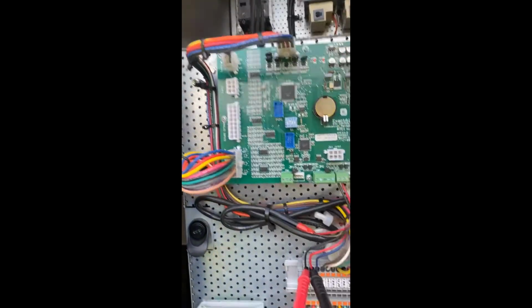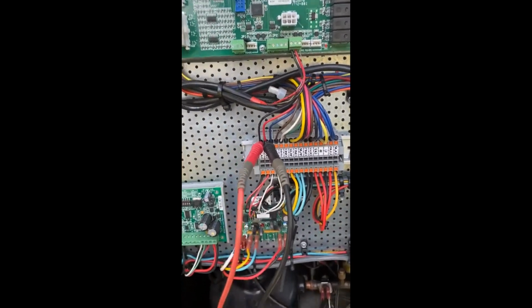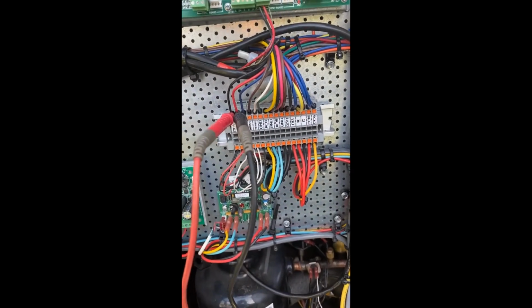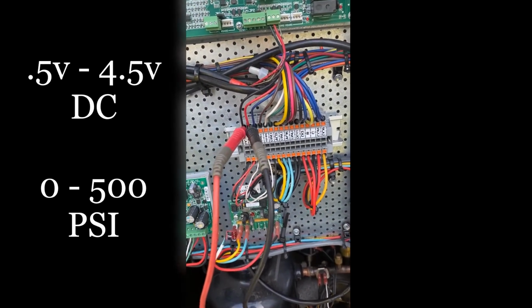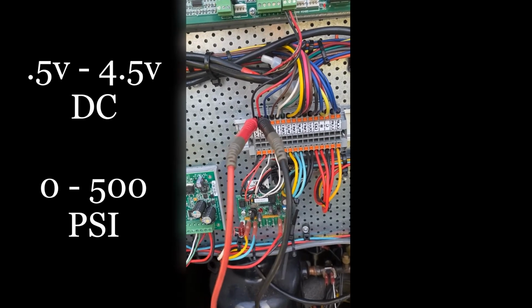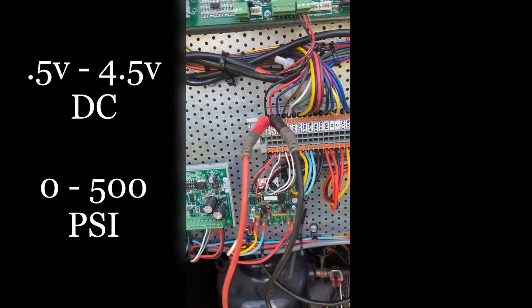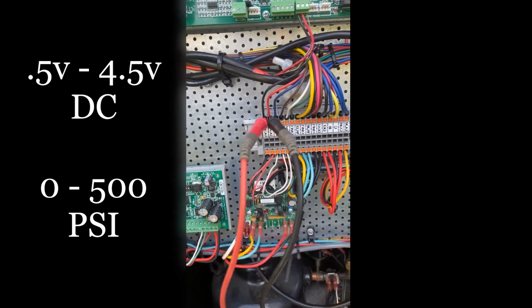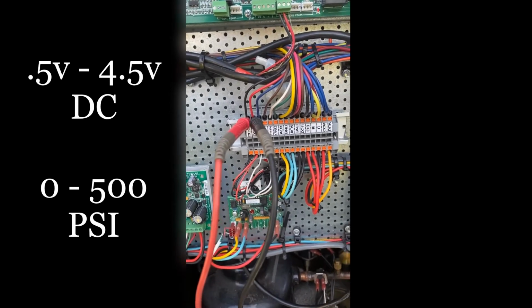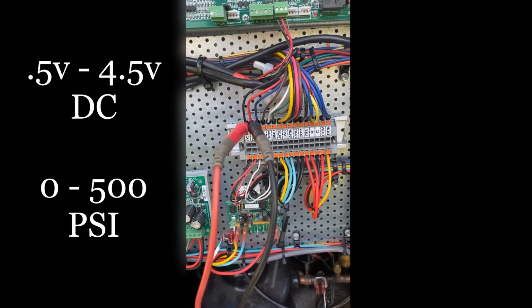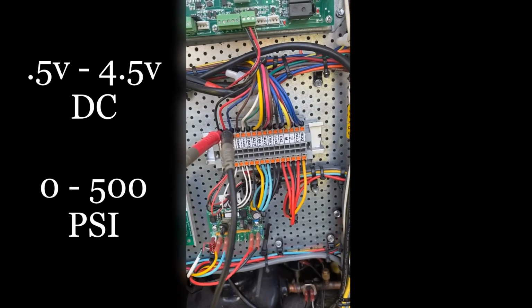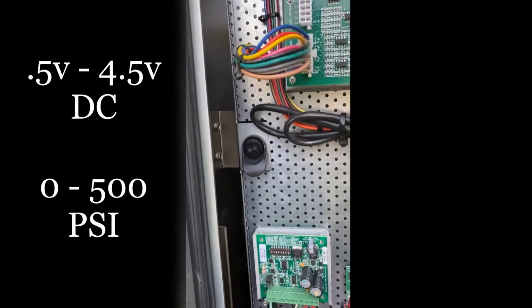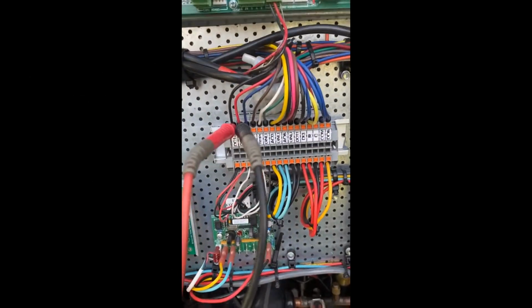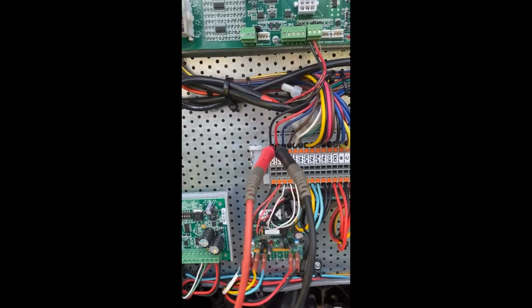So our board sends 5 volts DC through our suction transducer, and out the suction transducer, it should be at least half a volt to 4.5 volts, which is the rating on the transducer itself. Some are 0 to 5 volts, you know, so you have to look at your sensor. So this one should have at least half a volt. I was getting no volts when I first checked it, and it was bad. And I'll show you how I checked it.